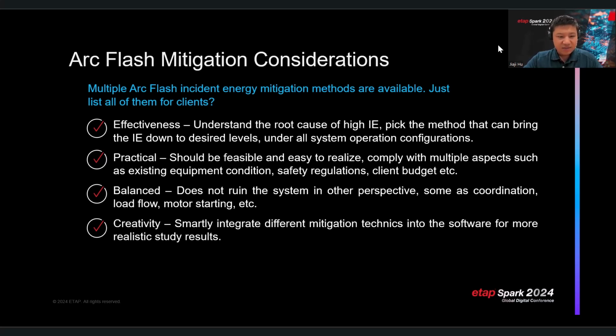The third one is about balance. Any recommendation we are giving, we should not ruin the condition of the system, such as load flow stability, your protective coordination, or even your motor starting, as we're gonna discuss later. Even if sometimes we need to compromise some aspects, it should be fully considered and evaluated.